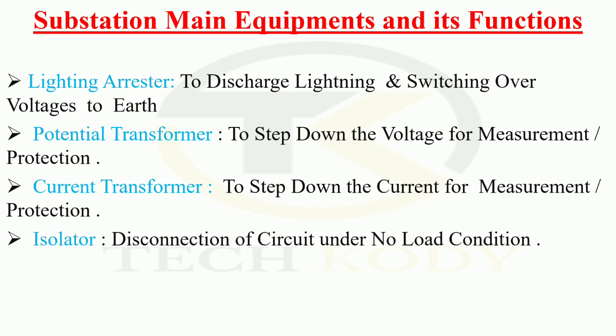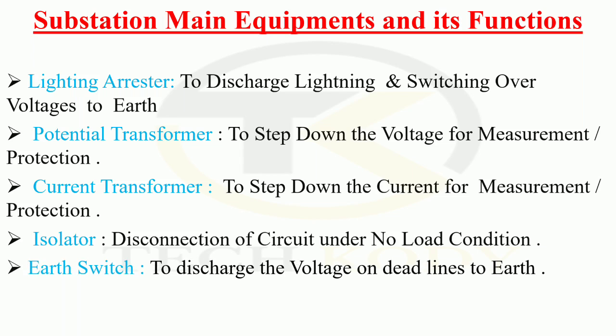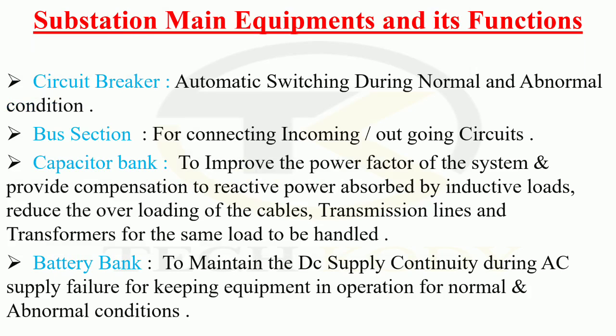Isolator: disconnection of circuit under no load condition. Earth switch: to discharge the voltage on dead line to earth. Circuit breaker: automatic switch during normal and abnormal conditions. Bus section: for connecting incoming or outgoing circuits. Capacitor bank: to improve the power factor of the system, provide compensation to reactive power absorbed by inductive loads, reducing the overload of the cables, transmission lines and transformers for the same load to be handled.